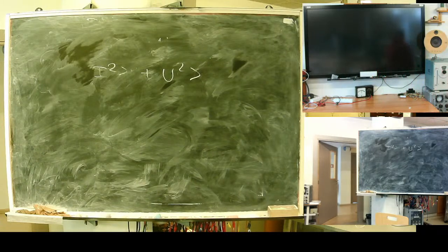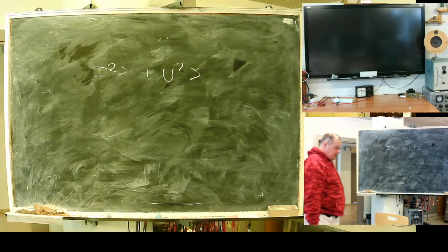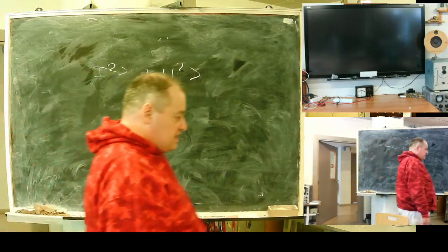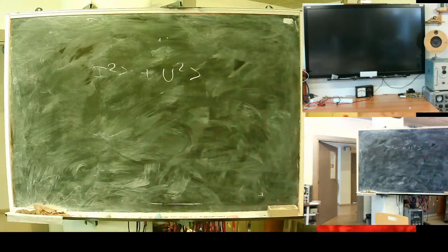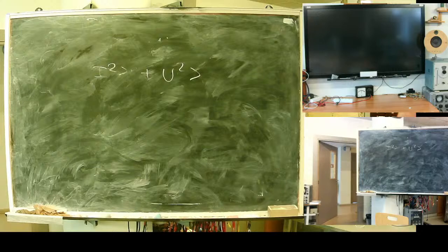Faults were observed, real faults, when a simultaneous three-phase fault occurred. How? A 110 kilovolt tower stands in the middle of a field. A farmer doesn't like missing part of his land, so he used this tower as a storage place for fertilizer.